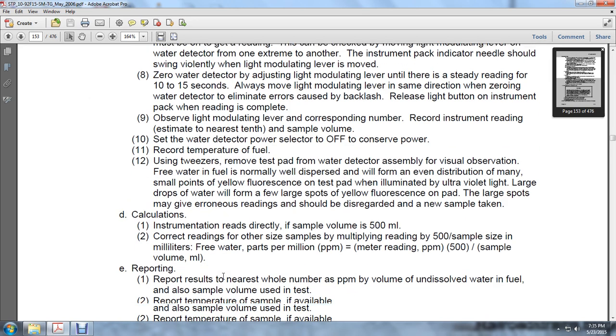Calculations. The instrument reading is read directly if the sample is 500 milliliters. Correct readings for sample sizes other than 500 by multiplying the reading by 500 divided by the sample size in milliliters. Free water in parts per million equals the meter reading in parts per million times 500 divided by the sample volume in milliliters. Report the result to the nearest whole number as parts per million by volume of undissolved water in the fuel. Also report the sample volume used in the test. Report the temperature of the sample, if available.